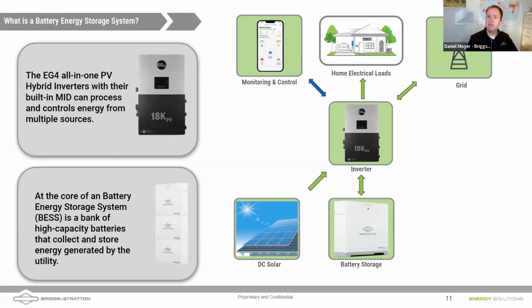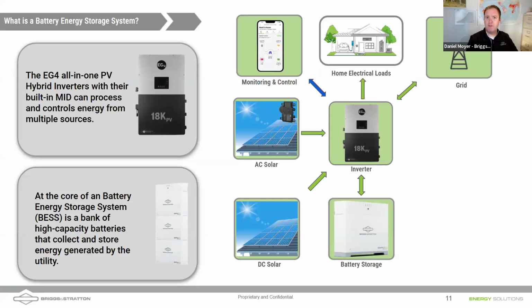net metering anymore. We can bring in AC coupled solar. This is great for coming out to a site that already has maybe some Enphase microinverters or a SolarEdge string inverter. Bring it into the gen port on these hybrid inverters. When the grid goes out, the inverter disconnects us from grid using energy stored in the batteries. Again, can power the home load, but also create a microgrid in the home that the AC coupled solar just recognizes as grid and will continue to operate. When the batteries start to get full, the loads are satisfied, we can use frequency shifting to adjust the AC sine wave to start to curtail some of that AC coupled solar.